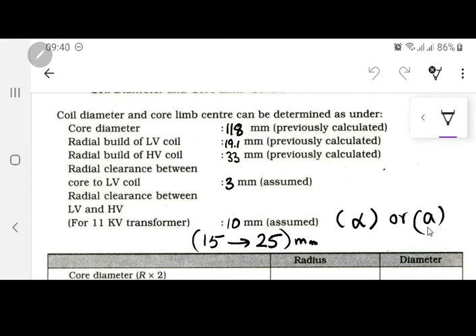This means that you can play with this variable and change your percentage X, because the percentage X formula, which I will prove in the next class, has this parameter alpha or A inside it. So if you reduce this A parameter, you are reducing the gap between the low voltage winding and the high voltage winding. So practically the leakage flux is increasing and the percentage X is increasing if you are increasing this gap.